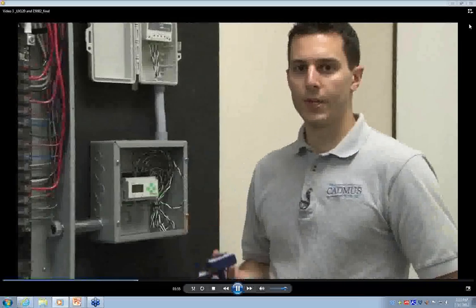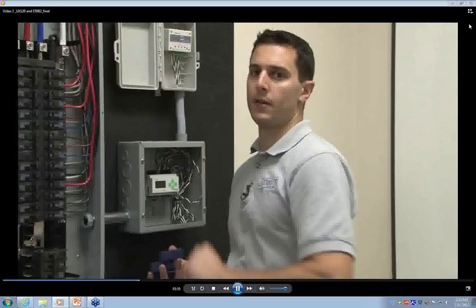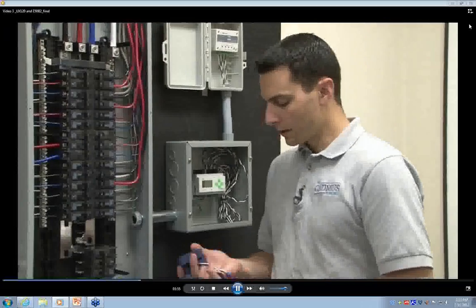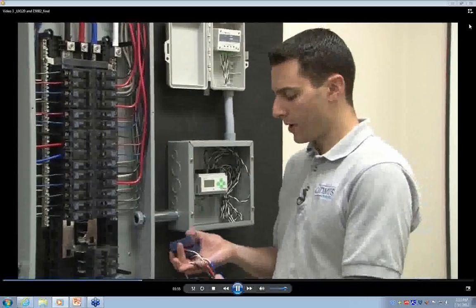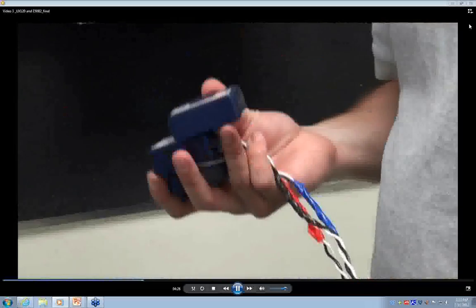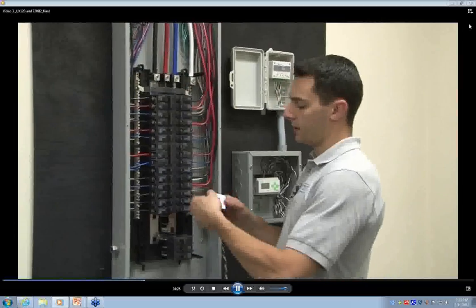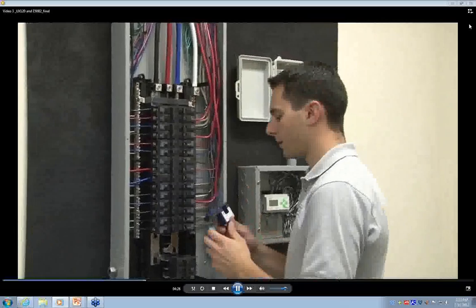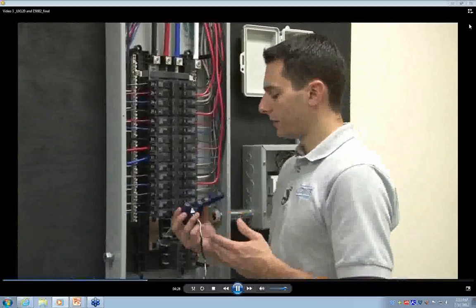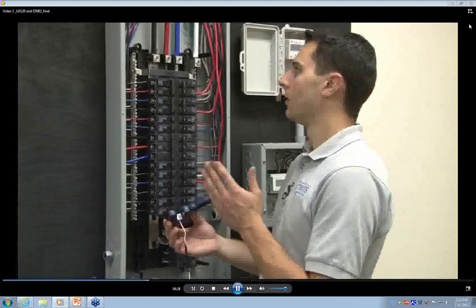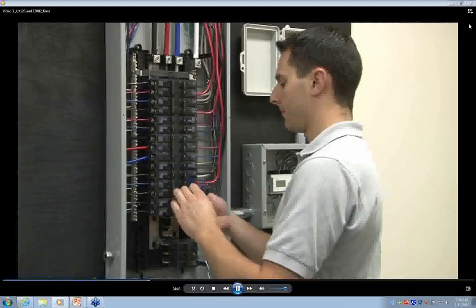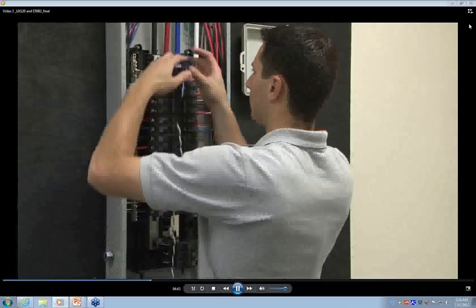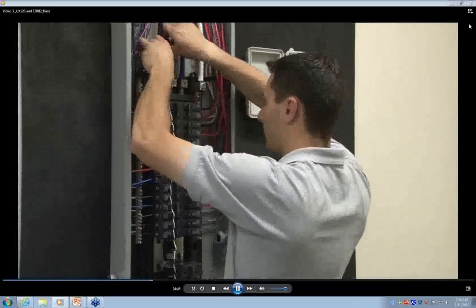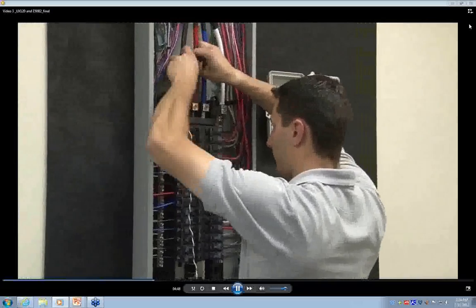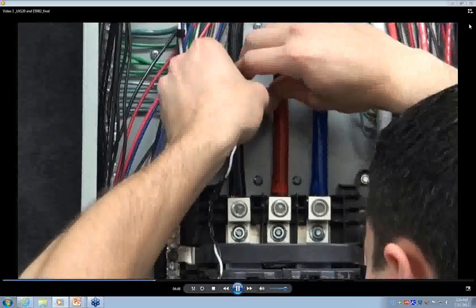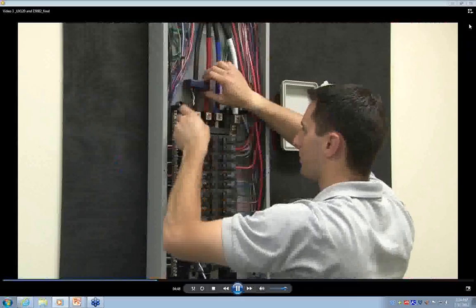We can now install our 3 CTs on the main feed of our panel. Once again, these CTs are color-coded, black, red, and blue, with our 3 phase conductors. We'll start with the phase A CT on the phase A conductor. These CTs are directional, and it's important that the arrow faces the source, or in this case, faces up. And these CTs just clip closed.